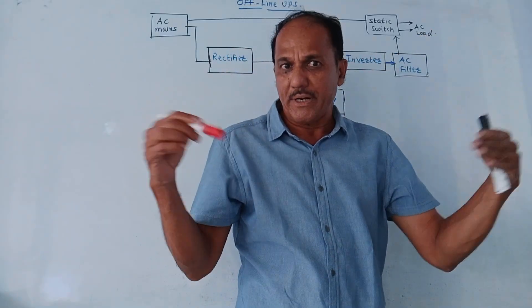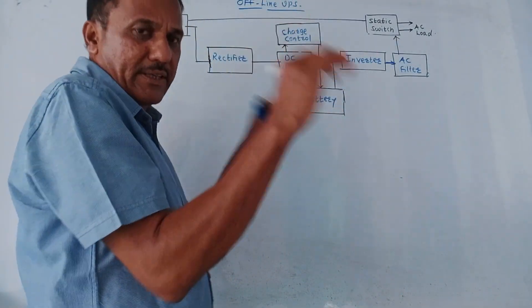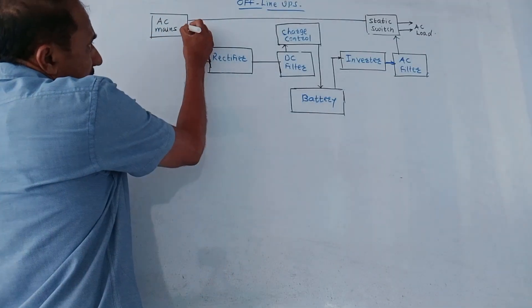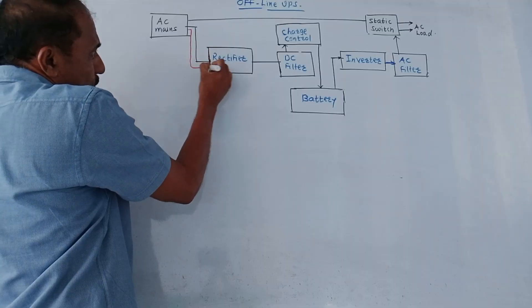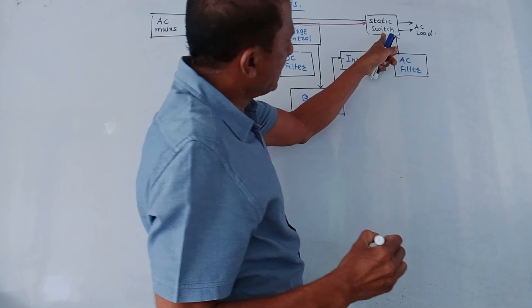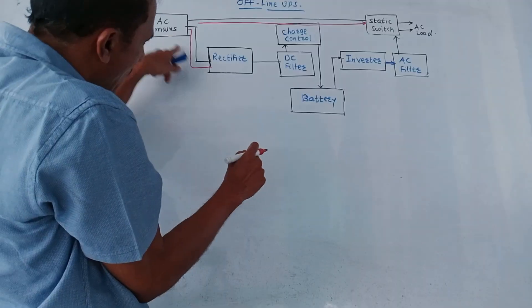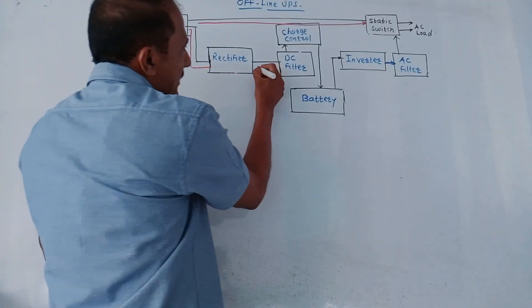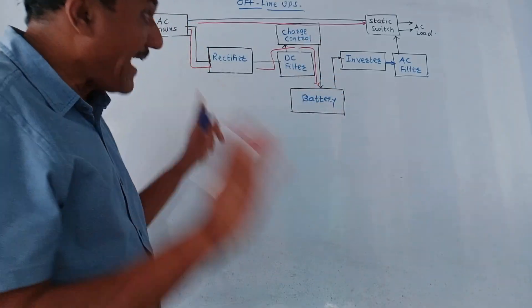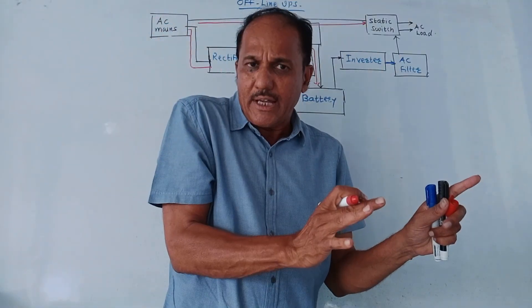The AC load is operated directly by AC mains under normal circumstances whenever there is continuous input power. At the same time, this power from AC mains is also applied to the rectifier — this is the normal operation. The power directly goes to the static switch and then to the AC load. Under normal circumstances, the same AC input is applied to the rectifier, then to the DC filter, then to the charge control unit, to charge the battery. But unlike online UPS, the inverter is not connected.